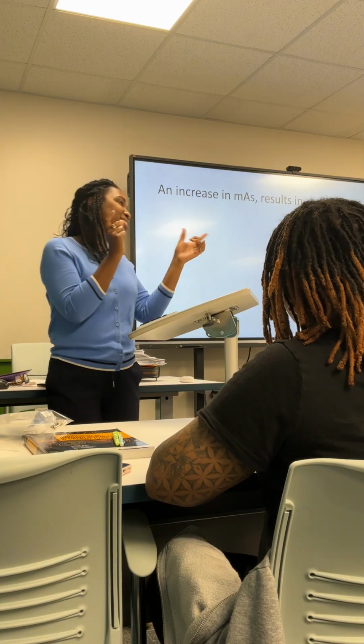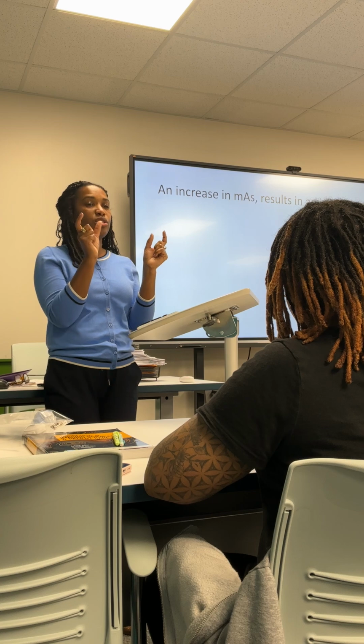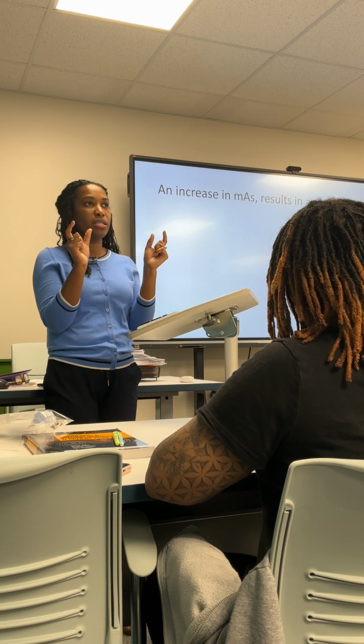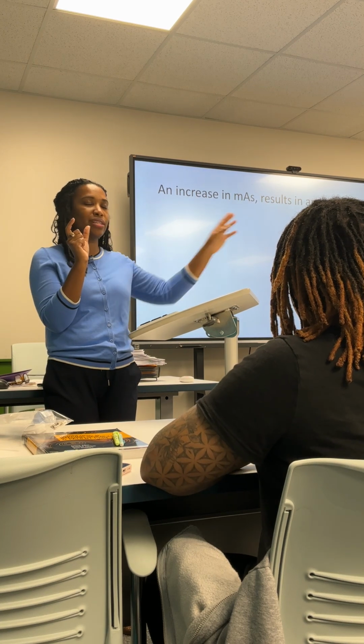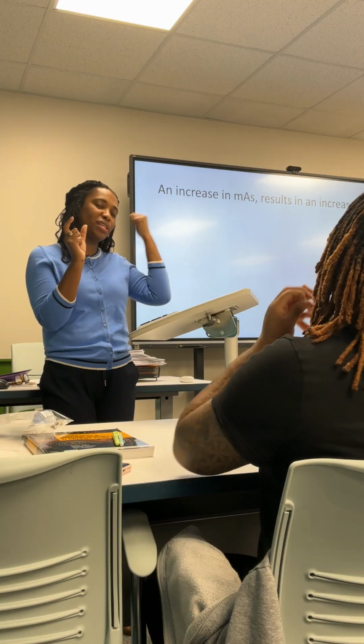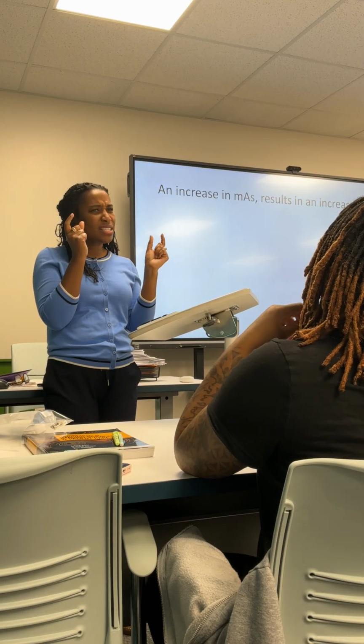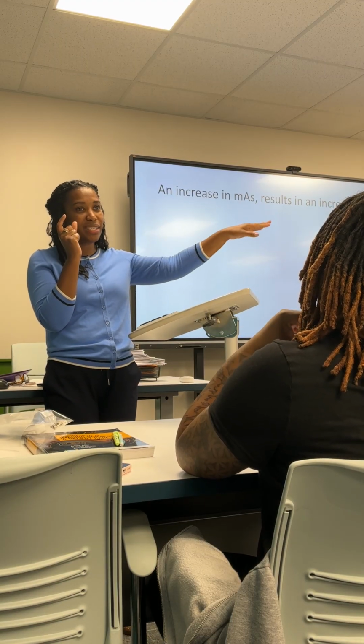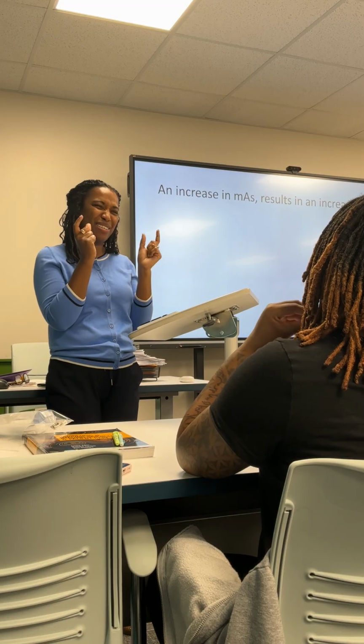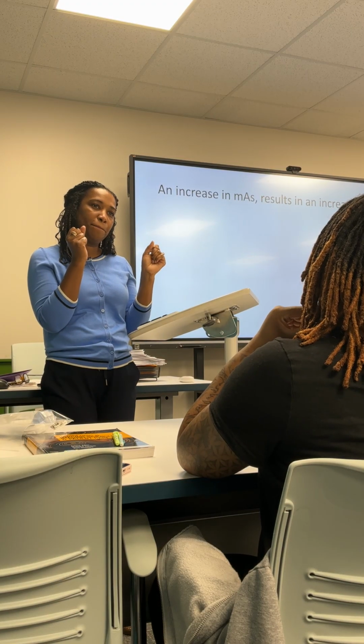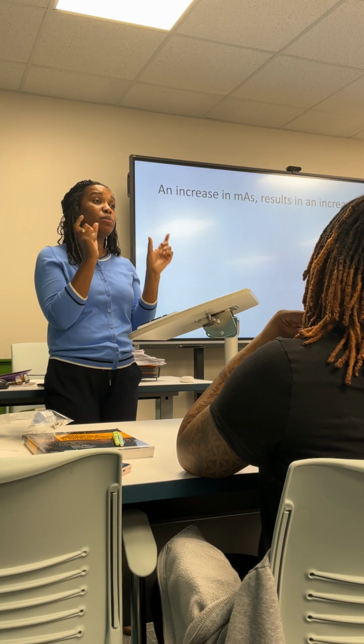Okay, yes, that's good. You picked that out of that. So increasing MAs increases the intensity, but does KVP as well? Yes, but at a different rate.